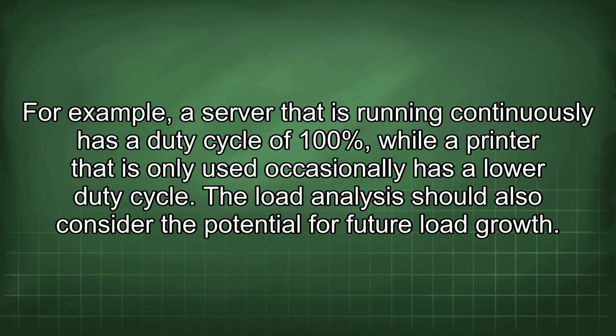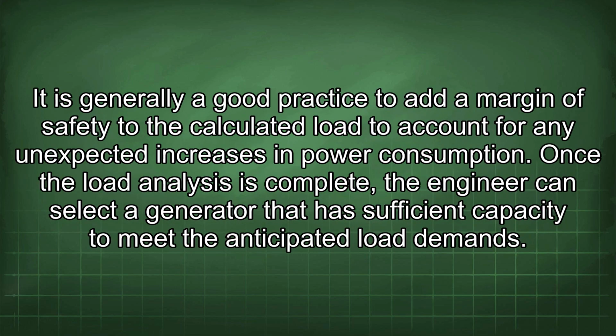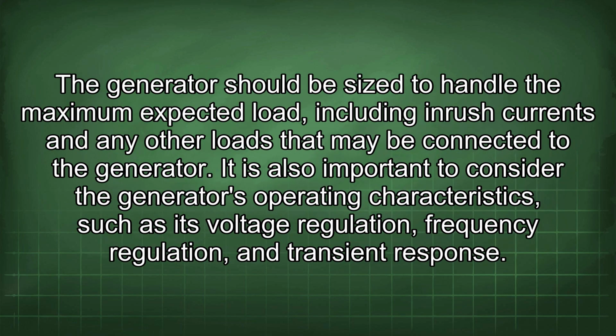The load analysis should also consider the potential for future load growth. It is generally a good practice to add a margin of safety to the calculated load to account for any unexpected increases in power consumption. Once the load analysis is complete, the engineer can select a generator that has sufficient capacity to meet the anticipated load demands. The generator should be sized to handle the maximum expected load, including inrush currents and any other loads that may be connected to the generator.